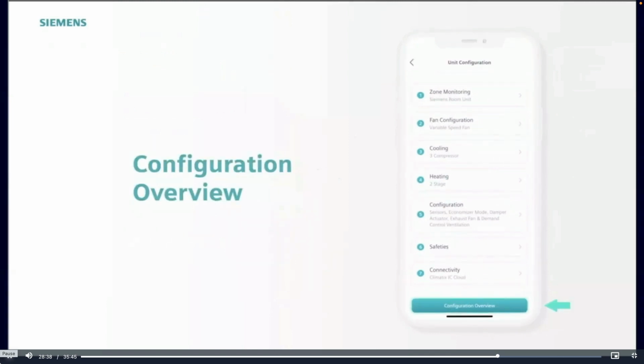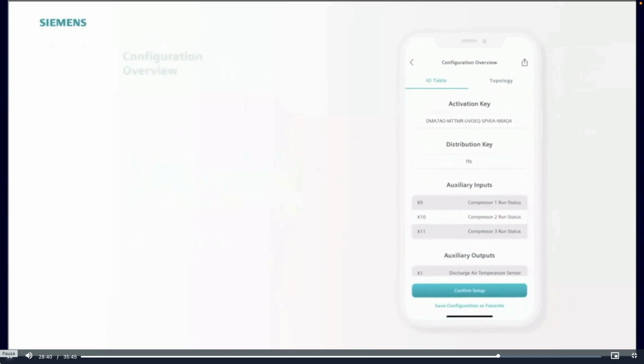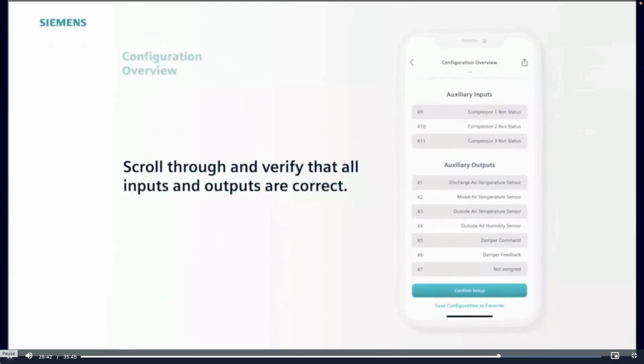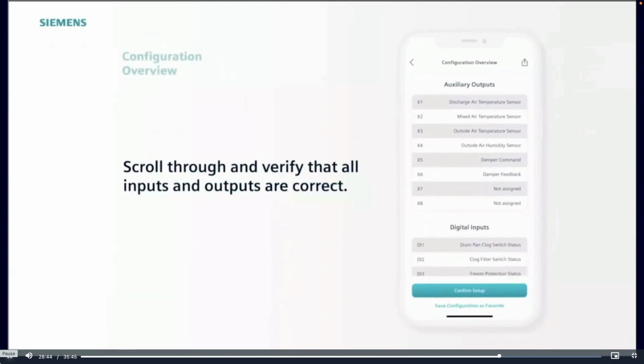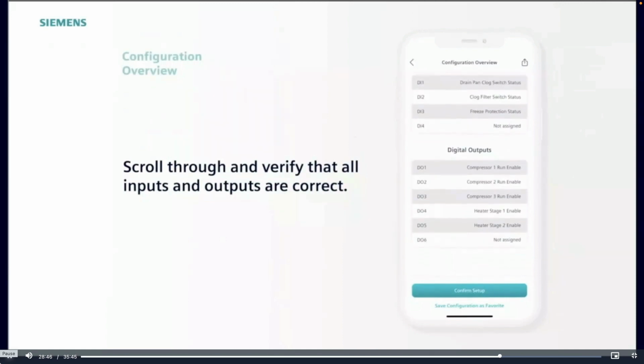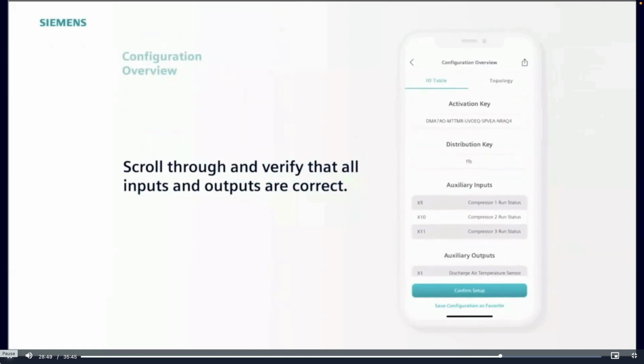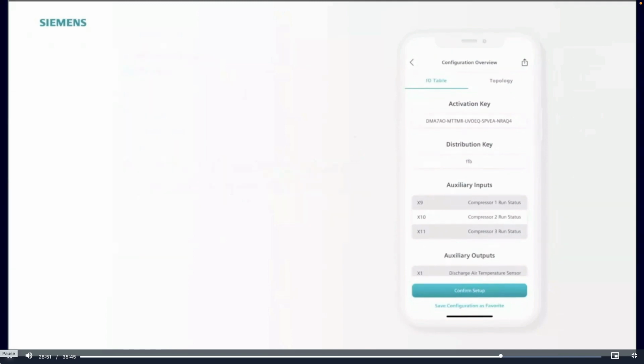Once through the 7 steps, tap Configuration Overview. Scroll through and check that all inputs and outputs are correct. We provide a printout of the default configuration with the controller, or you could print this out, laminate, and mount inside the unit for anyone to see at a glance.